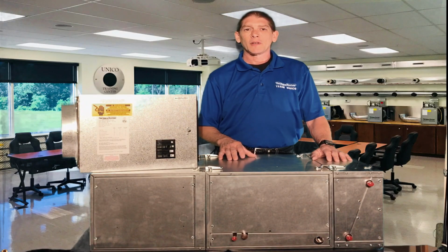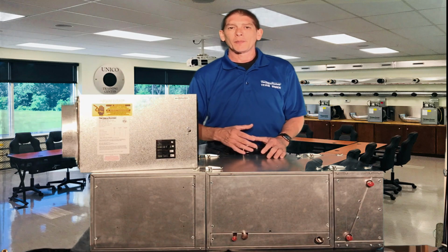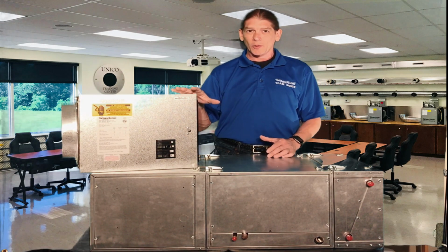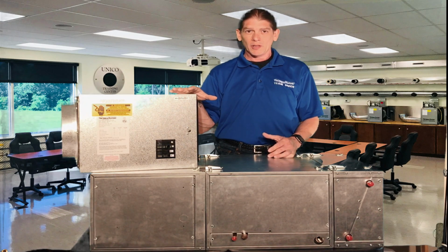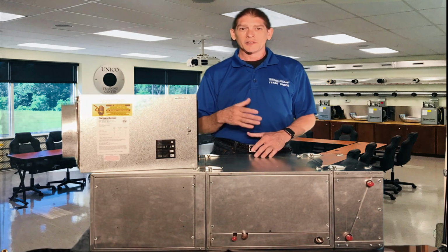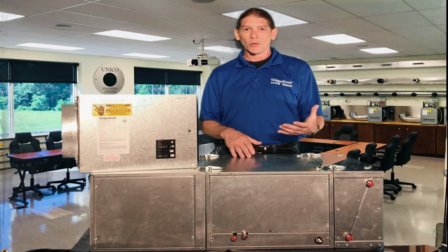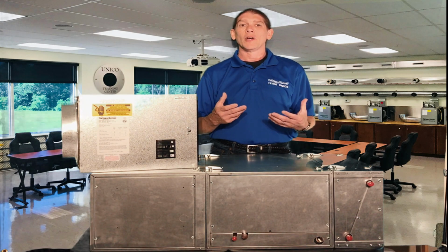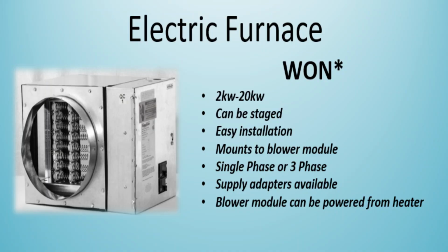Depending on the climate, sometimes supplemental or backup heat is necessary. This is a great option when the heat pump goes into defrost. When the heat pump goes into defrost, it is in air conditioning mode. Therefore, the indoor coil will become cold. There needs to be a way to temper the air so it doesn't drop the temperature in the space. The electric heater can also be used as a primary source of heat.